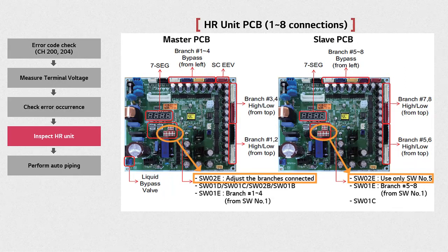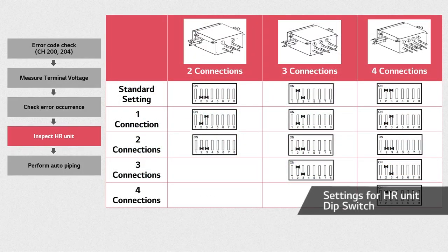On the other hand, for 8-branch HR units, the setting for the indoor units can be done by modifying the master main PCB's DIP switch, numbers 2, 3, and 4. A picture of an 8-branch HR unit's PCB is shown. The DIP switch has to be set according to the number of indoor units and branches connected. For example, when a 4-connection model is connected to 3 connections, switch number 2 should be on and switch number 3 should be off, as shown in the picture.